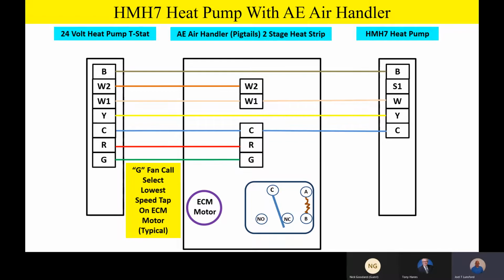The G terminal is going to be our fan, and typically on the ECM air handler, on the AE air handler, with that ECM motor, typically G will be selected for the lowest speed tap. The reason we recommend that is so if the homeowner has some indoor air quality devices, let's say they have an electronic air cleaner or some media filters that they want to circulate the air in the home all the time. If we put G on the lowest tap, so if they go to the thermostat subbase assembly and they call for fan only operation just to circulate the air, we want that air at the lowest airflow possible. That way it's nice and quiet and comfortable. And in addition, it makes the filtration systems work better. So G is typically going to be the lowest speed tap on the ECM motor.